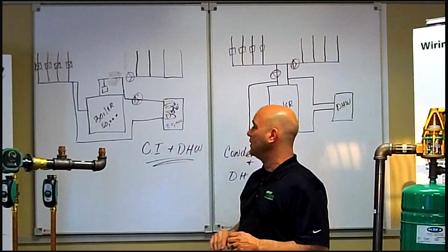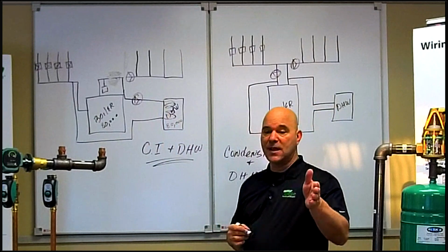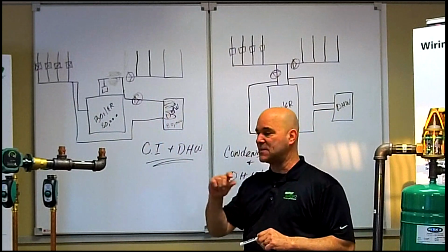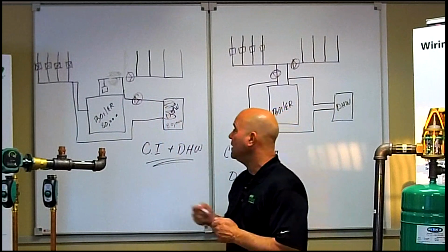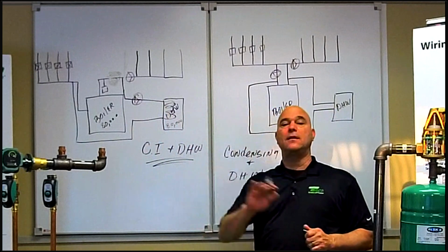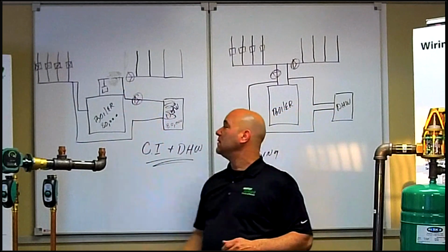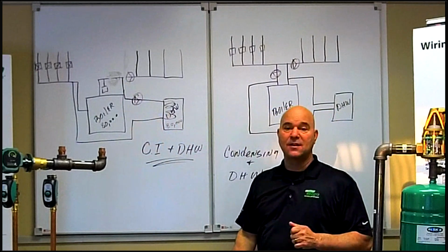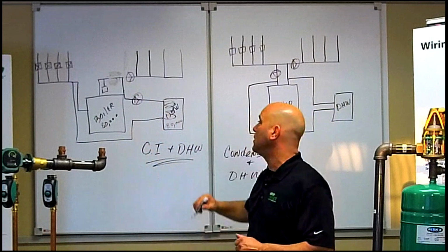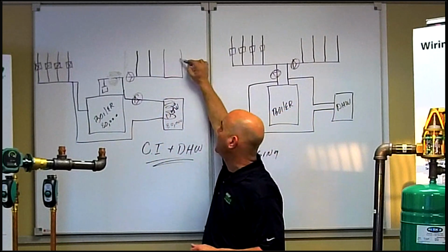So that's what it would look like if you look to your TACO book, or I know we sent out the pipe sizes with the delta T's. If we were looking at this, I've got 80,000 BTU. You can start firing answers off to Jim. I'd like to know what size my supply header and return header would be to handle the 80,000 BTU. You could also fire off to Jim what size our system heat circuits.